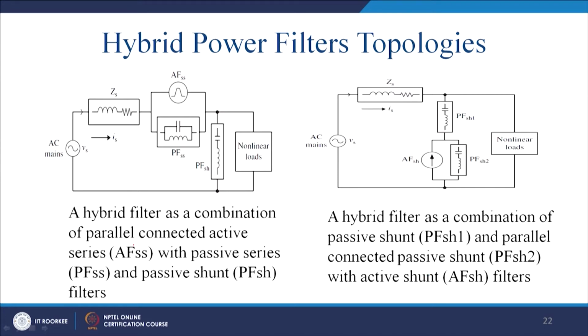A hybrid filter is a combination of parallel connected active series AFSS with passive series and passive shunt. There is, you see here, this is the source, harmonic source, because of that the source inductance. Then this will mitigate the harmonic voltages, and this also will mitigate the harmonic voltages, and whatever harmonic current will be there, since that harmonic voltage is less, this will be sunk into it. And this is the combination where this is double tuned, as you have seen in case of the passive filter.